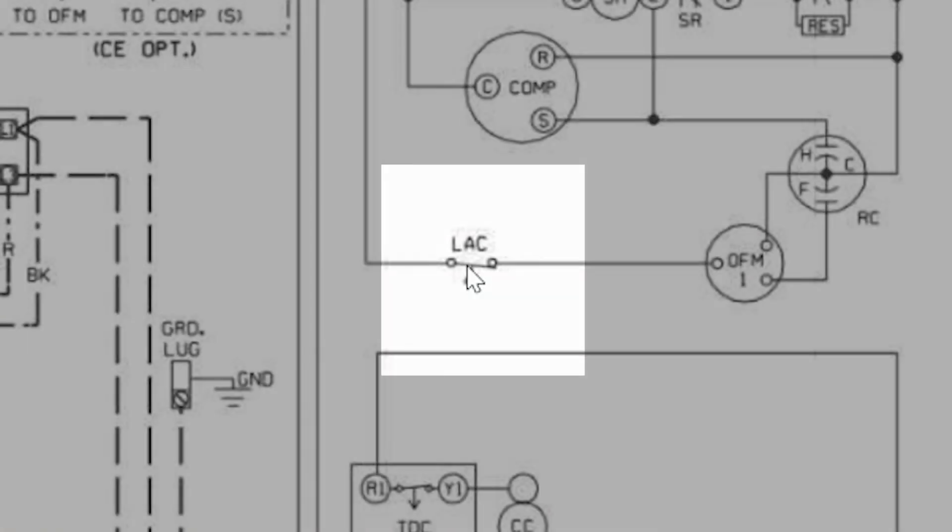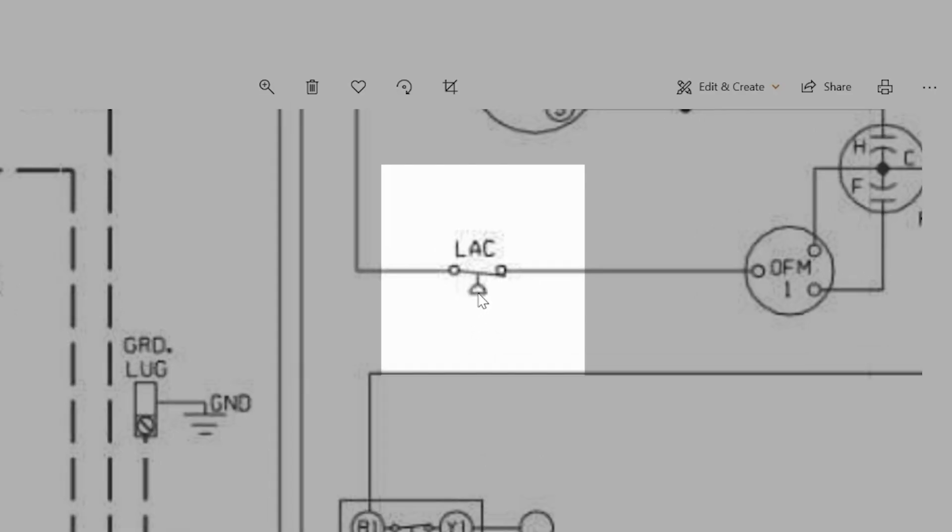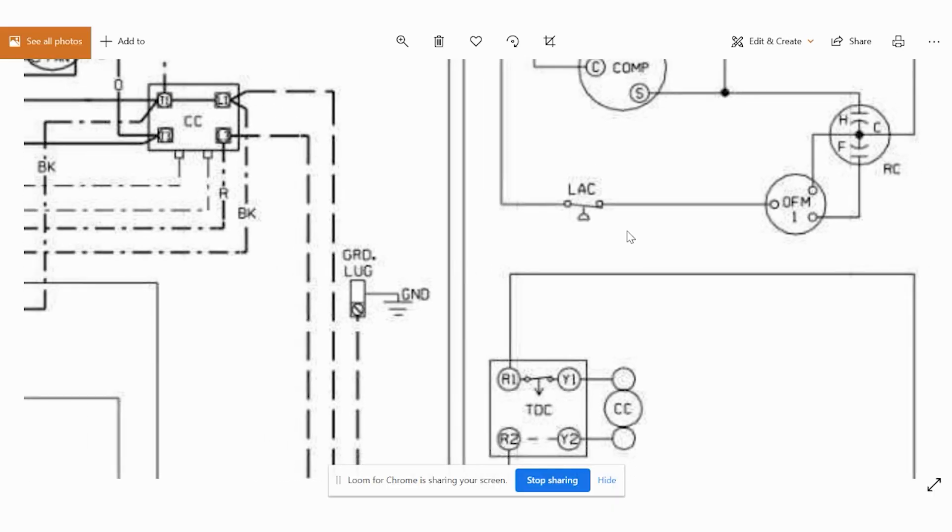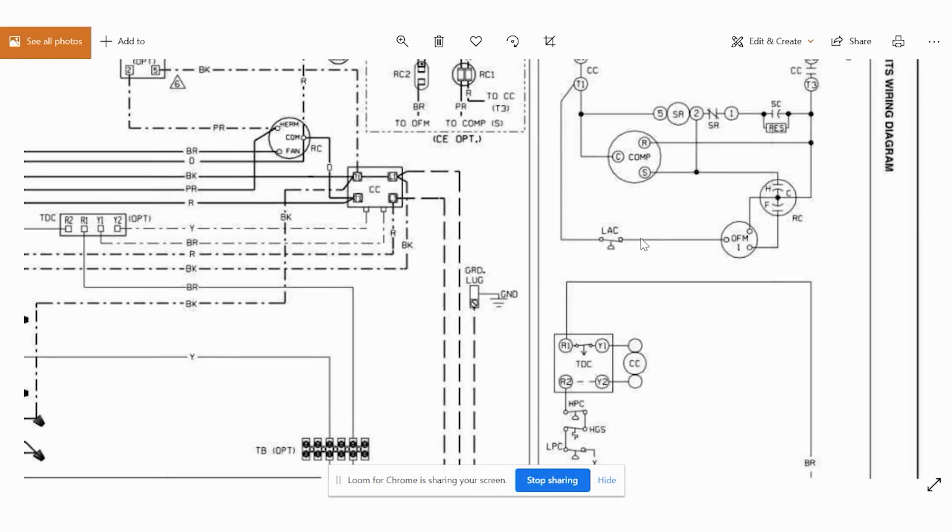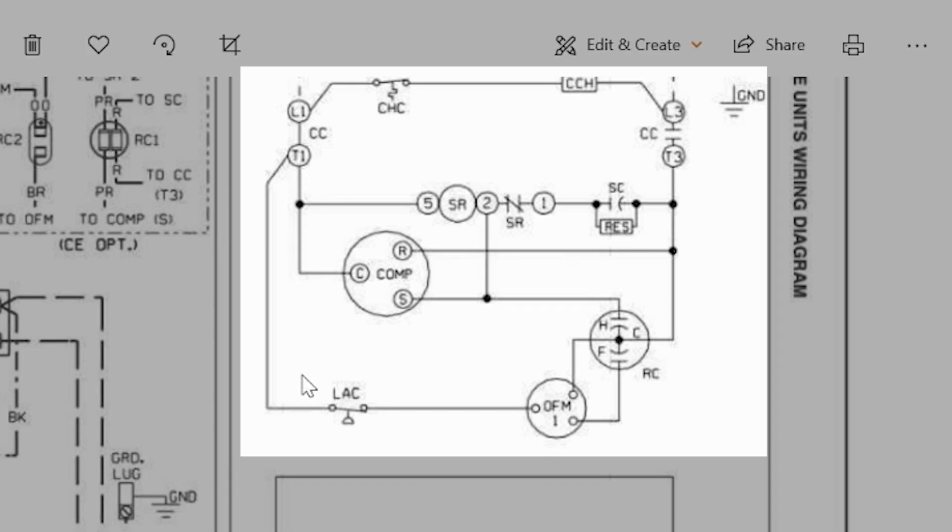Once again, here it says LAC. We can see that this is a single pole, single throw, open on fall pressure switch. This symbol means a pressure switch. If this pressure drops, then it's going to open the circuit. And let's look at what it's going to open the circuit to. We can see it's going to break the circuit to our common on our outdoor fan motor.